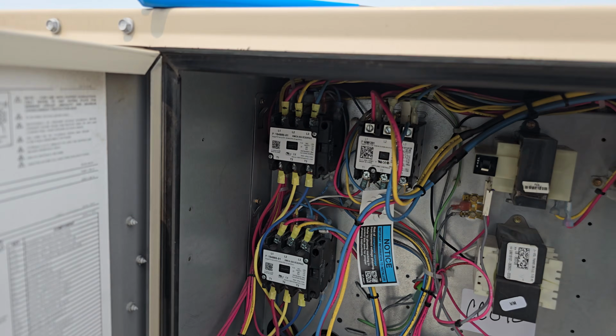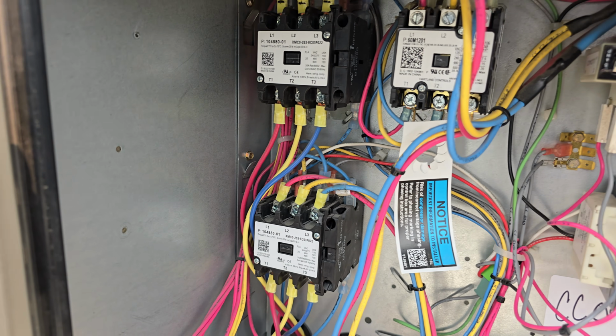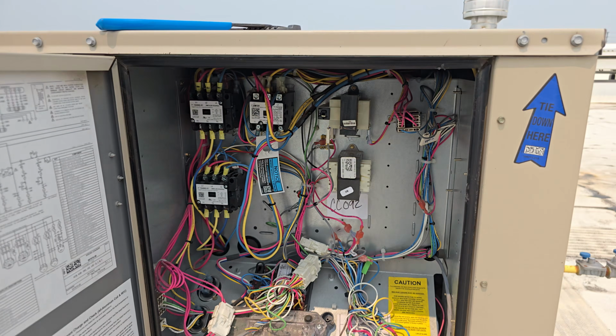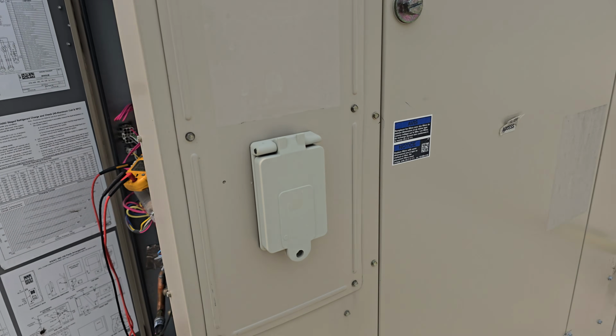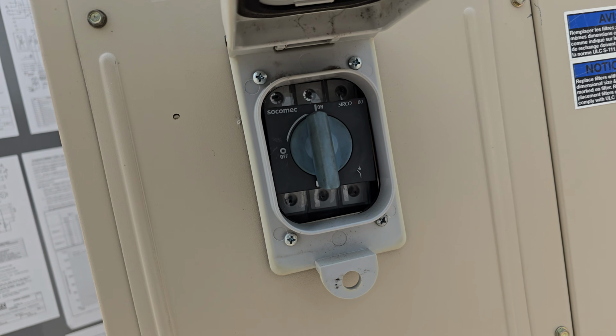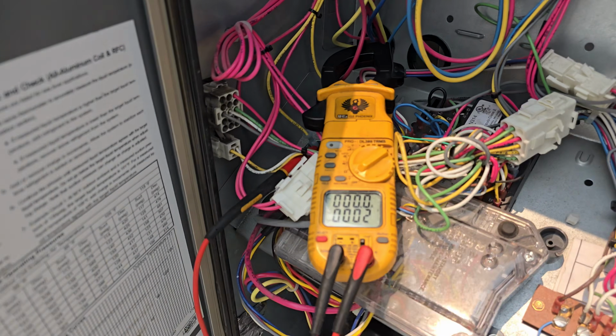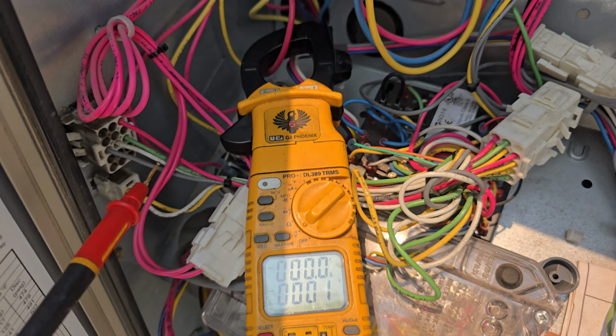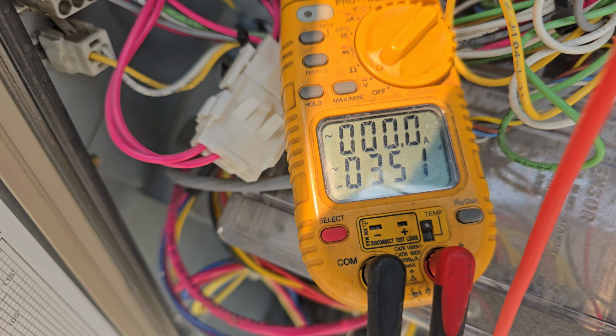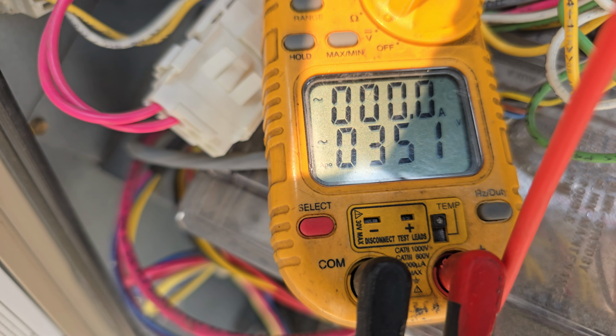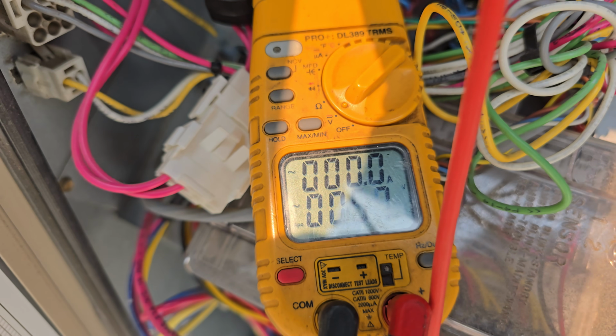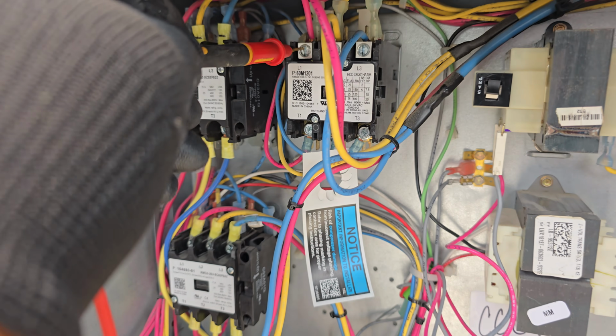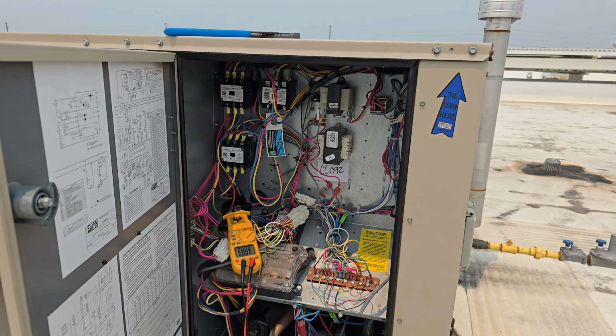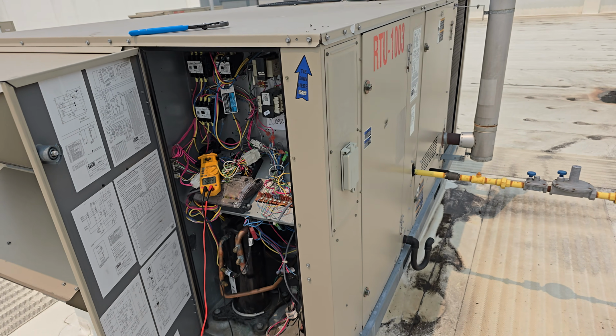But first, before I work on that, I'm going to see if I have power coming in here. Here is my switch to the unit. You can see it's in the on position, and I have set up my voltmeter. I'm going to read and see if I have power to all the phases. Here I have 351 volts, and to the next, the same 351, and to the next one 351. So I have voltage coming on all phases. I have three phase coming in, which is good. Power is really coming in here.